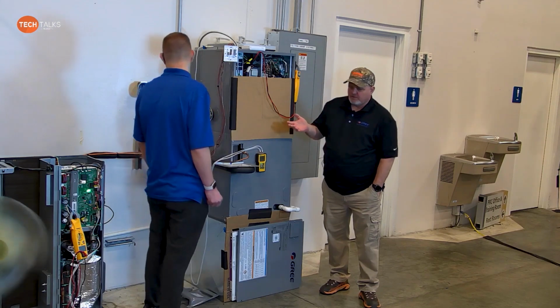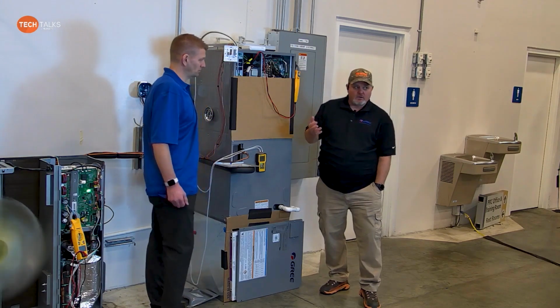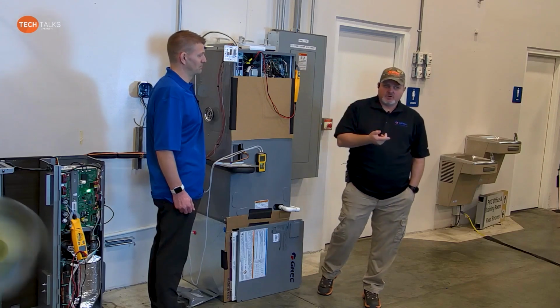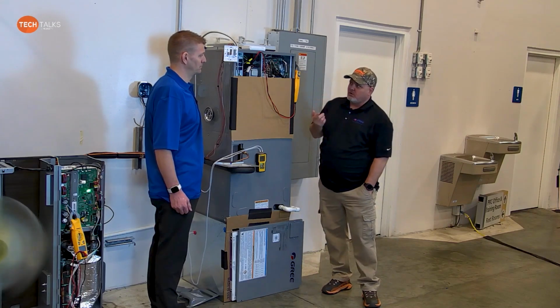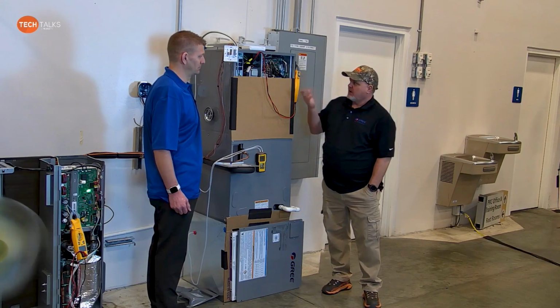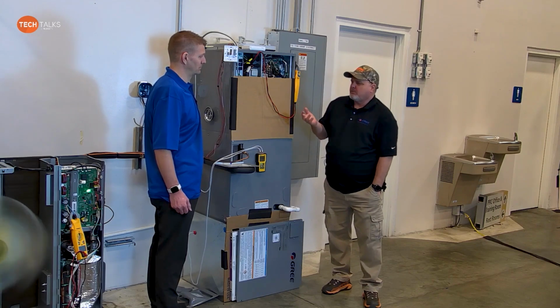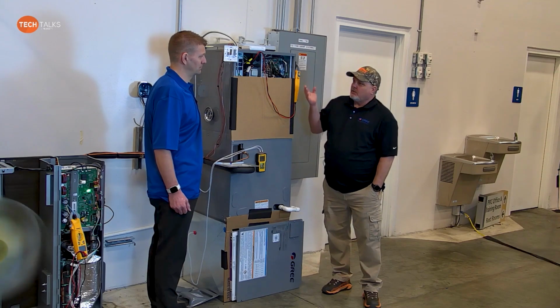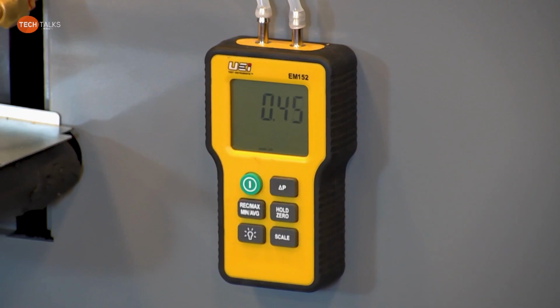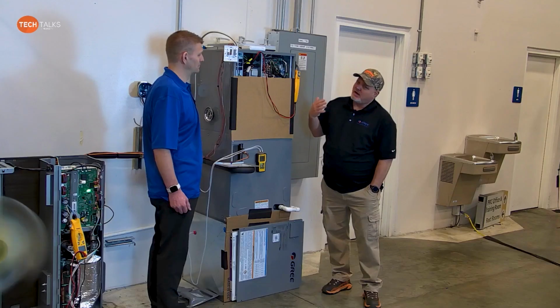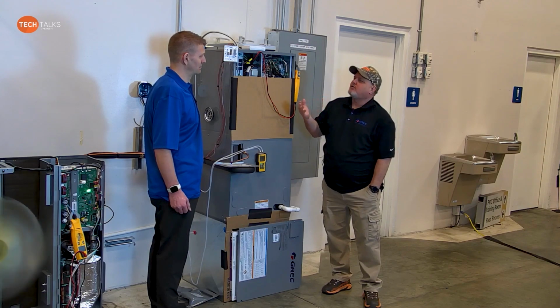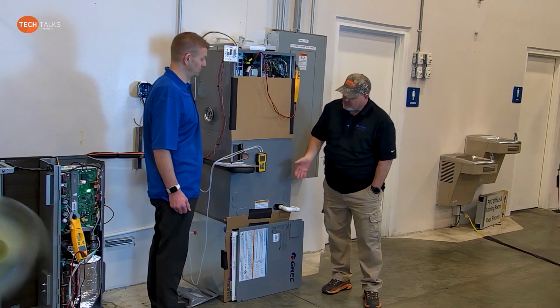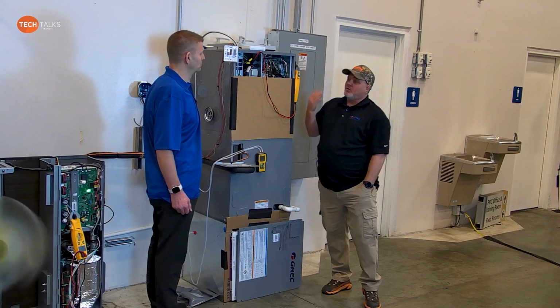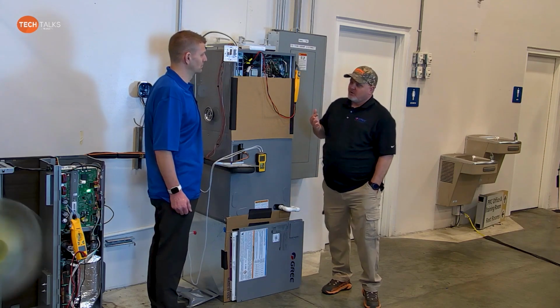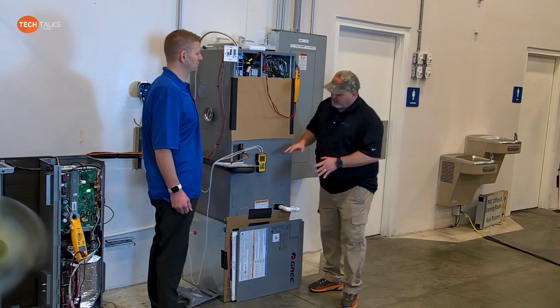It'll take a minute for it to cycle off. Meanwhile, we're going to go back to the shared screen again. I'm going to show you what we're going to be doing here. We have to wait for it to cycle off. We could probably even just kill power, but then we're going to reset the dip switches. We're going to give it a higher blower profile. So I'm actually increasing the torque level of the motor. Let's see what happens to the static pressure if we go to a higher fan speed setting. In my opinion, I'm giving you a crude example.